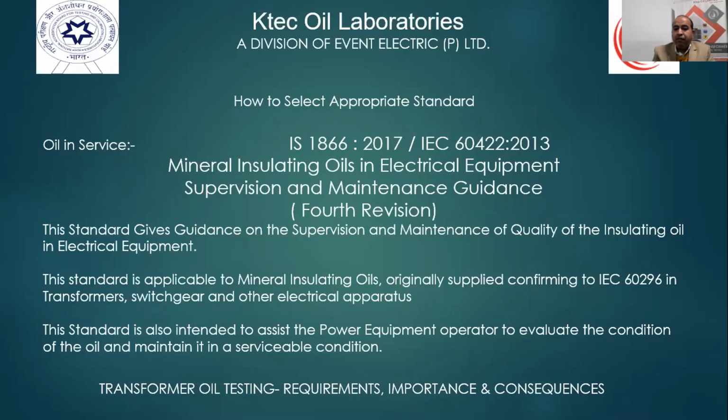It is when we have used that oil in the transformer. There are 2 conditions. I'll explain each and every condition. This standard gives guidance on the supervision and maintenance of quality of insulating oil in electrical equipment, originally supplied conforming to IS 335. This is applicable where only IS 1866:2017, which is the latest revision.